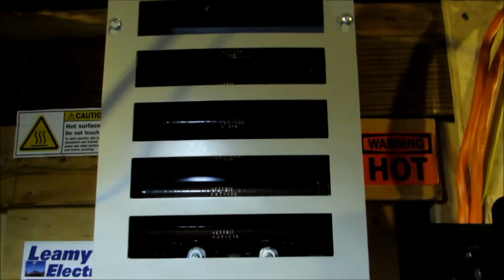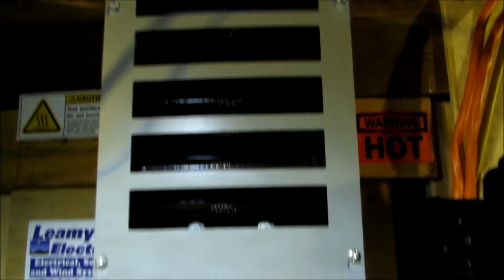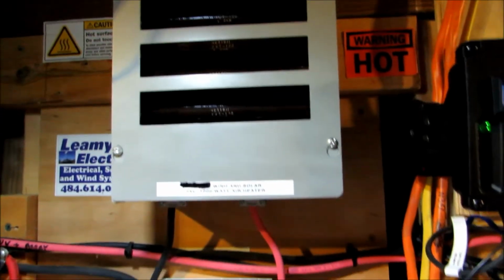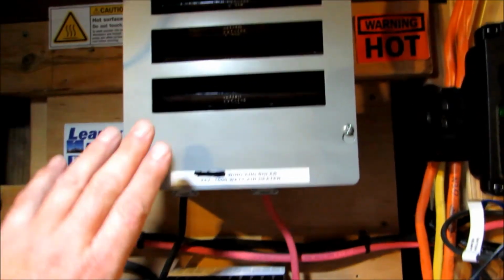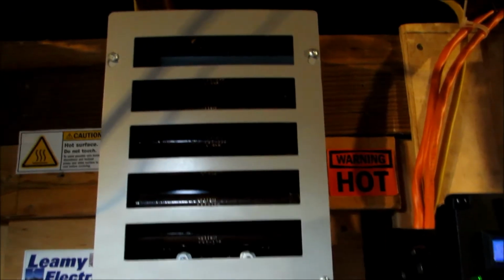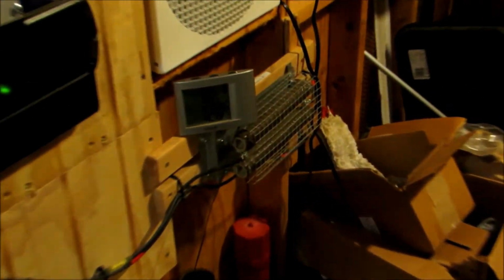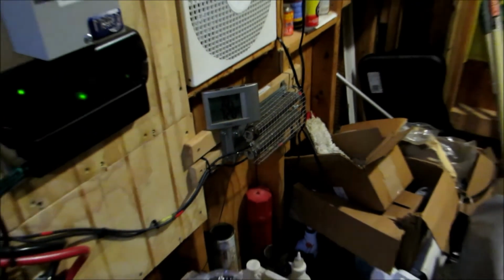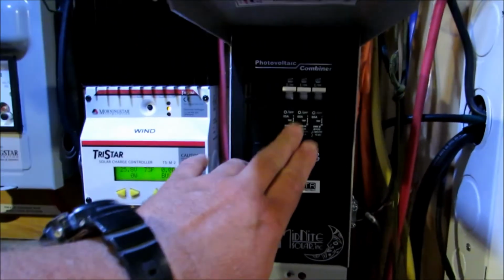And a 60 amp breaker for my solar air heater, or diversion dump load resistor load. That's where the excess power out of the battery bank goes if you get too much of a surge of wind. You get a lot of wind, it comes right here into my resistors. And also here, I got about another 600 watts of resistors. That is also for diversion from wind, and that's coming straight out of the battery bank, through these breakers here.